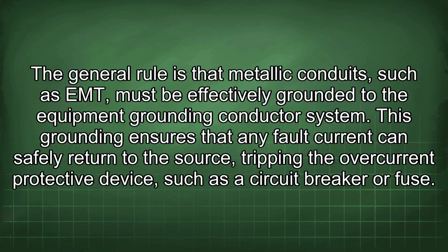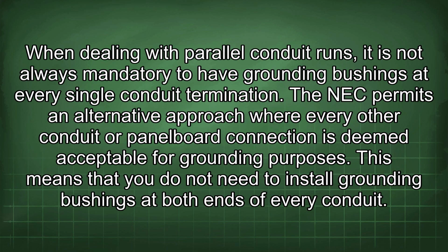The general rule is that metallic conduits, such as EMT, must be effectively grounded to the equipment grounding conductor system. This grounding ensures that any fault current can safely return to the source, tripping the overcurrent protective device, such as the circuit breaker or fuse. When dealing with parallel conduit runs, it is not always mandatory to have grounding bushings at every single conduit termination. The NEC permits an alternative approach where every other conduit or panel board connection is deemed acceptable for grounding purposes.